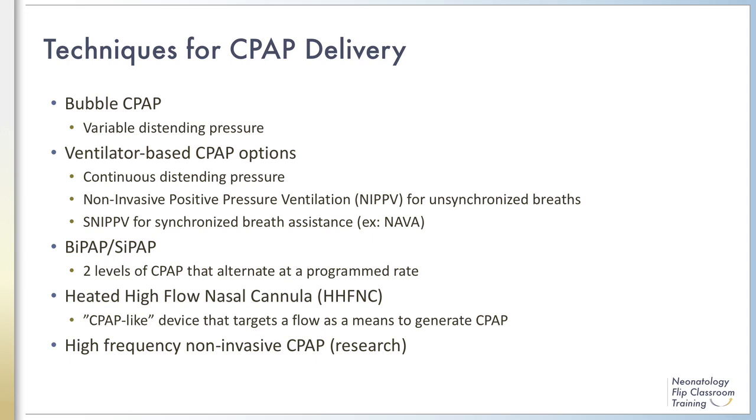BiPAP and SiPAP are modalities that use two levels of CPAP that are alternated at a rate chosen by the provider. BiPAP uses a straight change in pressure that looks like a square wave, whereas SiPAP creates a sinusoidal pressure wave with the high and low points set to the two different CPAP levels. Heated high-flow nasal cannula is a newer modality that delivers a humidified gas flow rate in liters per minute instead of a set pressure, and has some CPAP-like effects. Studies comparing high-flow nasal cannula and CPAP have mostly been small pilot studies without sufficient power. Experimental therapies with CPAP delivered via oscillating ventilators are ongoing.